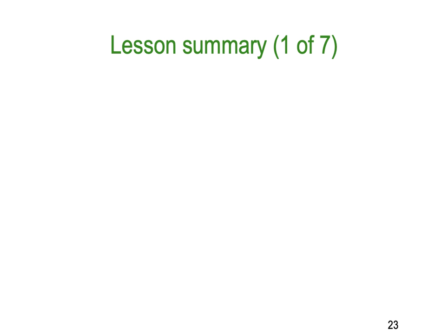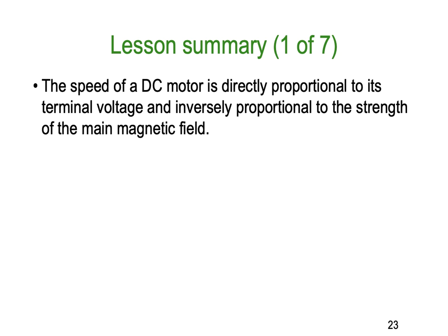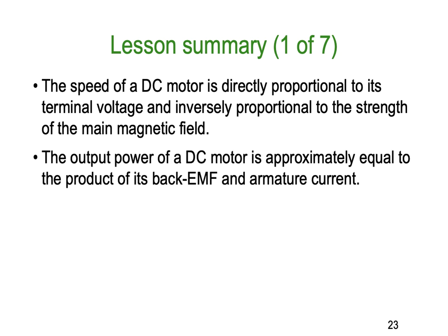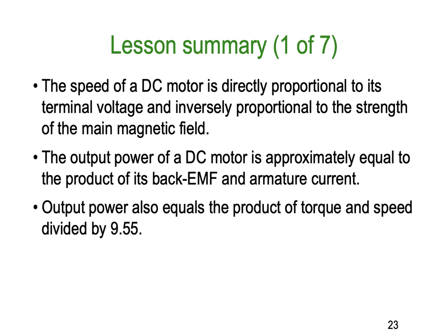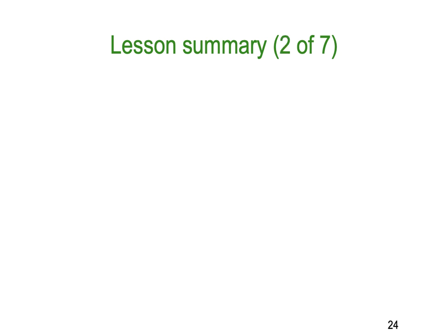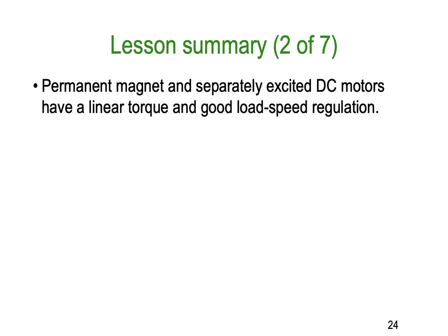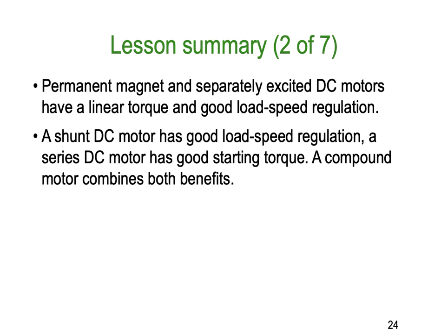Let's summarize. The speed of a DC motor is directly proportional to its terminal voltage and inversely proportional to the strength of the magnetic field. The output power of a DC motor is approximately equal to the product of the back EMF and the armature current. The output power also equals the product of torque and speed divided by 9.55. Permanent magnet and separately excited DC motors have nice linear torque and good load speed regulation. A shunt DC motor has good load speed regulation, a series DC motor has good starting torque, and a compound motor has a combination of both characteristics.